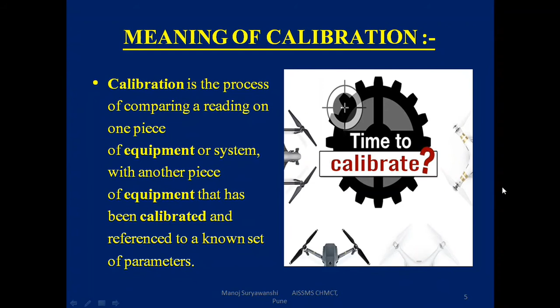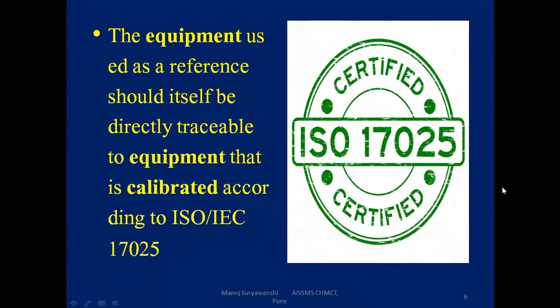The equipment used as a reference should itself be directly traceable to equipment that is calibrated according to ISO IEC 17025. As per the certified procedure of ISO 17025, the equipment has already been checked, verified physically and calibrated, and as per that reference we can cross check the in-house equipment.